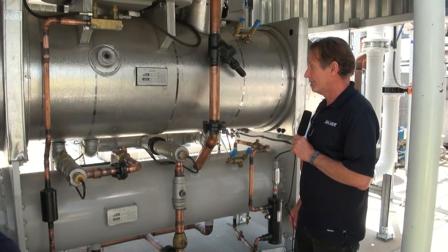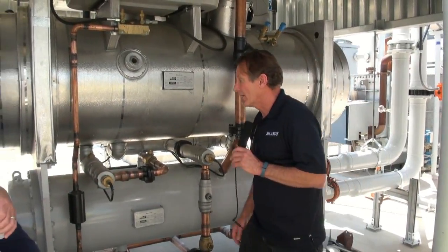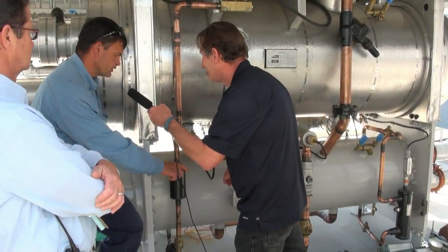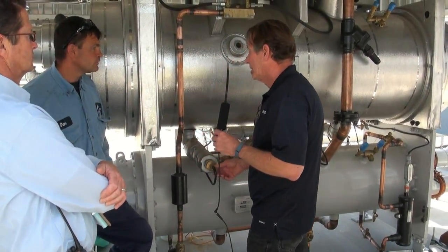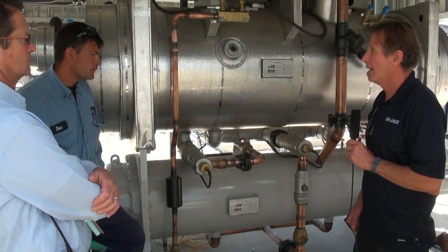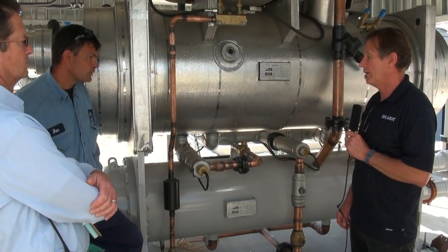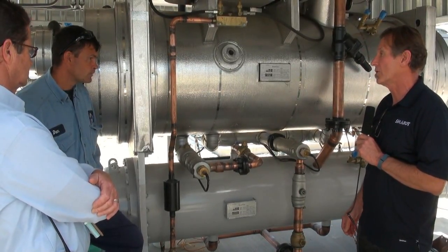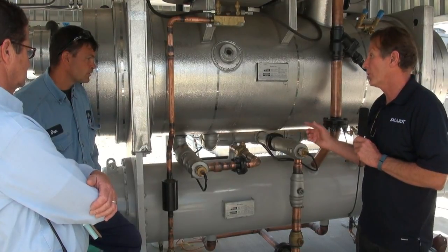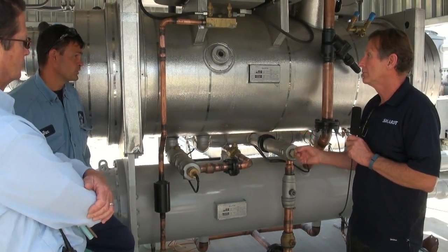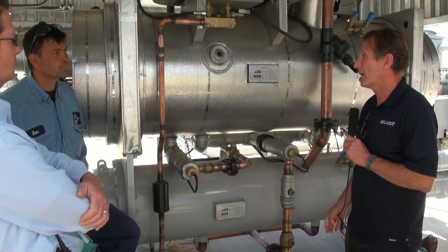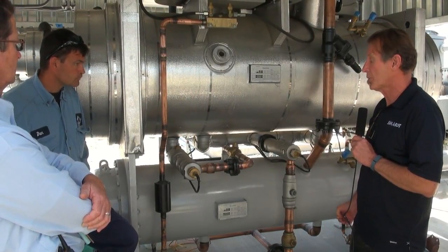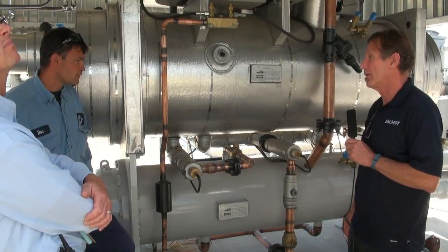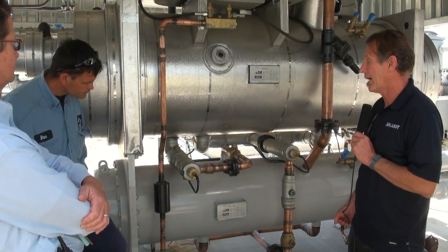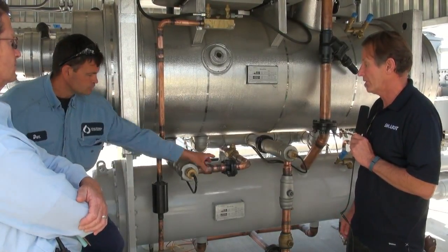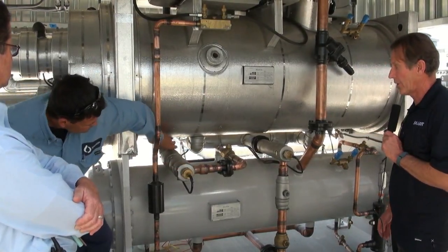Any questions, guys? What's that? How are you controlling hot gas? Temperature is the main control. You can set it so many degrees below set point, and it'll open. So you can set it up that way. It just depends on how it's configured. It depends on your application, on how you want to run the chiller, what's required for your application.